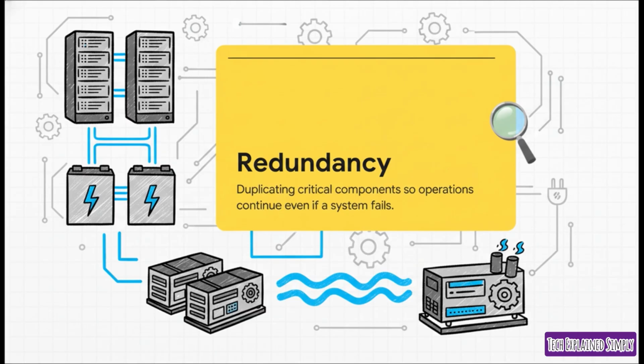So, to combat inevitable failures, they rely on redundancy, which simply means duplicating critical components so operations continue even if a system crashes. If the local city grid goes dark, massive uninterruptible power supplies, or UPS systems, instantly kick in with battery power. The servers don't even blink. Then, within seconds, these gigantic backup generators fire up to carry the entire load for as long as the blackout lasts. That guarantees zero downtime, period.